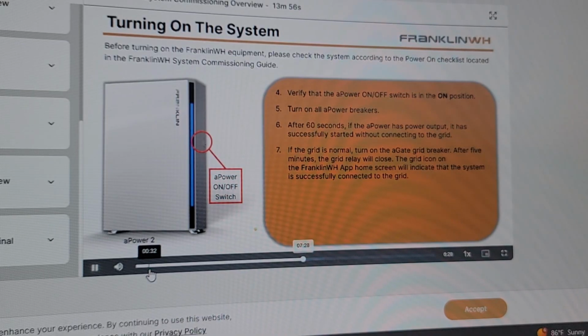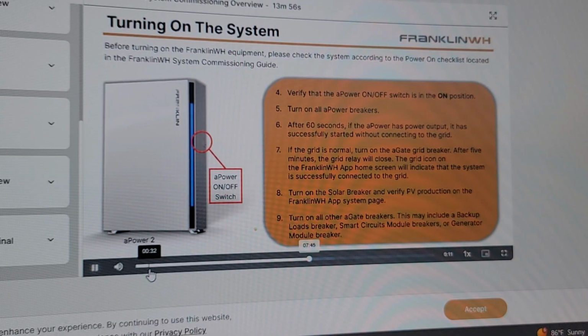After 5 minutes, the grid relay will close. The grid icon on the FranklinWH app home screen will indicate that the system is successfully connected to the grid. Step 8. Turn on the solar breaker and verify PV production on the FranklinWH app system page. Step 9. Turn on all other aGate breakers. This may include a backup loads breaker, smart circuits module breakers, or generator module breaker.